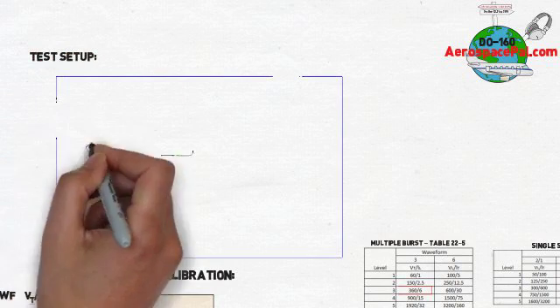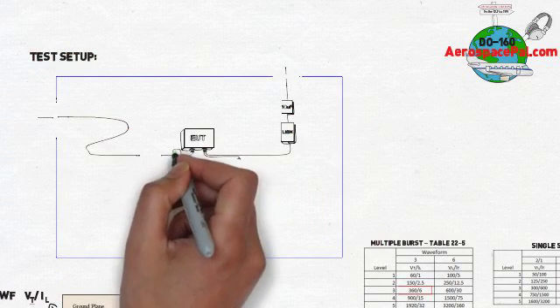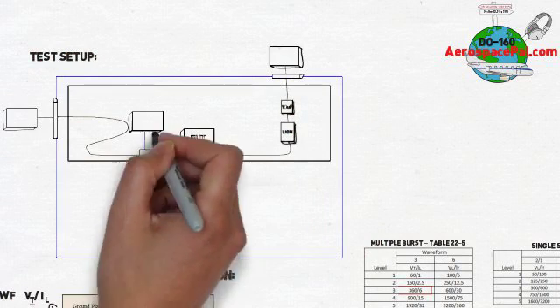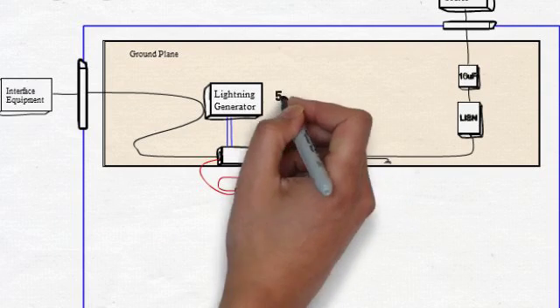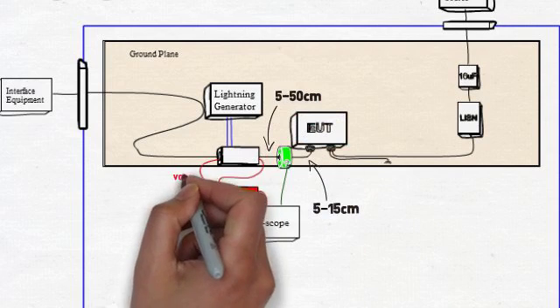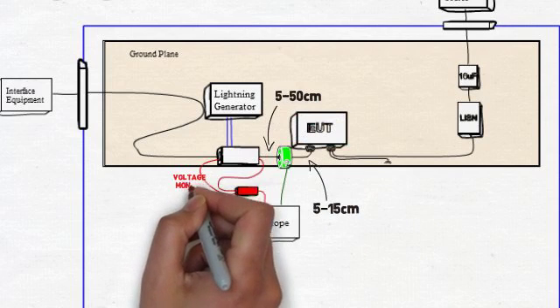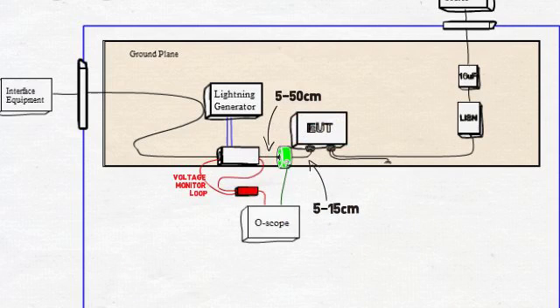The test setup for cable bundle is pretty straightforward as shown here. The current monitor needs to be 5 to 15 centimeters away from the EUT connector and the injection clamp needs to be 5 to 50 centimeters away from the current monitor. The voltage monitor is an open circuit loop around the injection clamp.